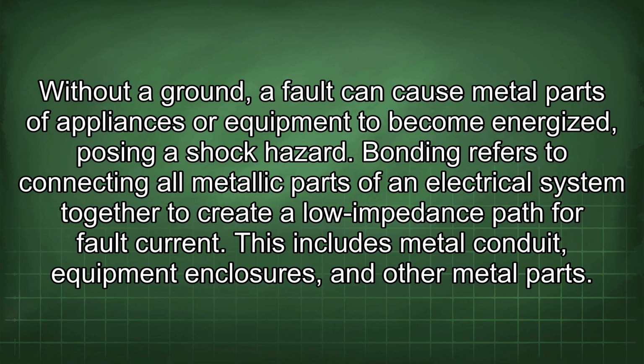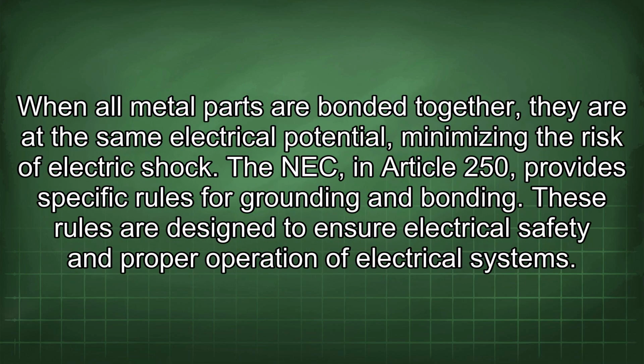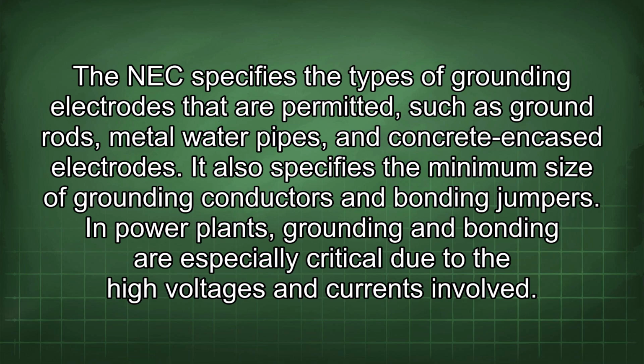Bonding refers to connecting all metallic parts of an electrical system together to create a low impedance path for fault current. This includes metal conduit, equipment enclosures, and other metal parts. When all metal parts are bonded together, they are at the same electrical potential, minimizing the risk of electric shock. The NEC in Article 250 provides specific rules for grounding and bonding. These rules are designed to ensure electrical safety and proper operation of electrical systems. The NEC specifies the types of grounding electrodes that are permitted, such as ground rods, metal water pipes, and concrete encased electrodes. It also specifies the minimum size of grounding conductors and bonding jumpers.